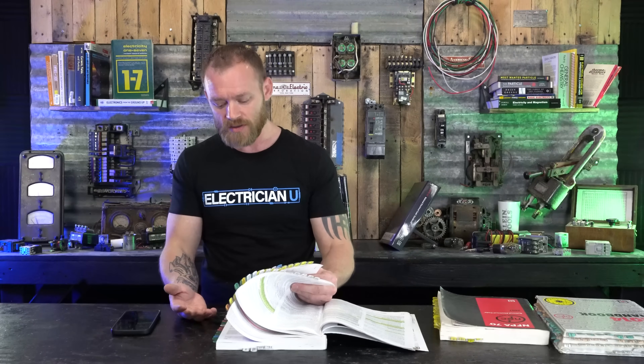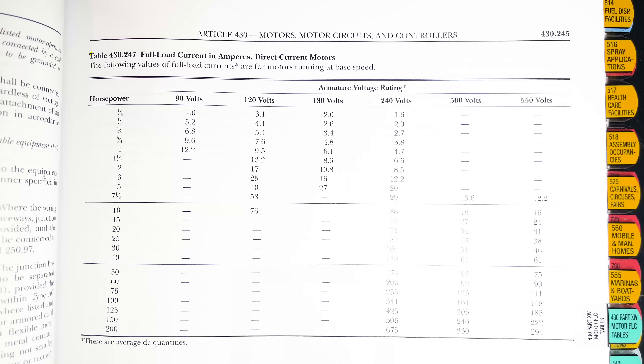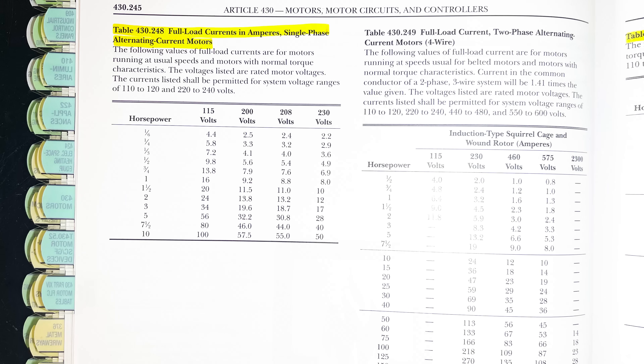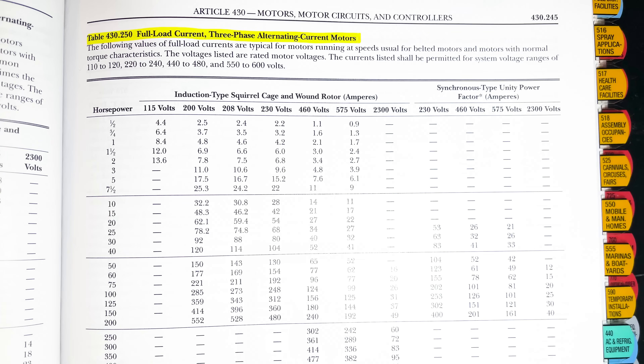I'm not going to go through every single one, but in the 430s for motors — 430.247, 248, 249, and 250 — I would highlight at least the three-phase alternating current and the single-phase alternating current tables because you're going to use those quite a bit.